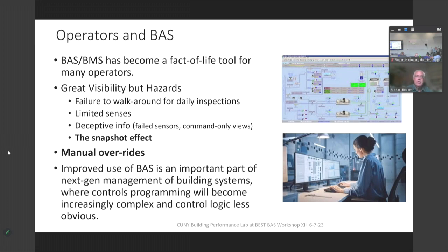There are some other things too, difficulties in when we see 0 and 100%. Is 0% fully closed or fully open? Is 100% closed or open? That sometimes can cause confusion. It's not always systematic across even the same plant, and it's not always labeled systematically. So there's some deceptive information we have to watch out for.